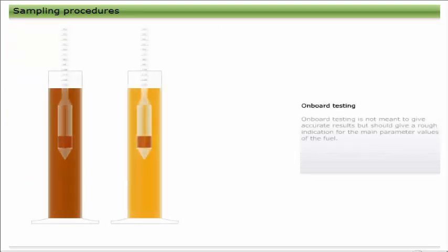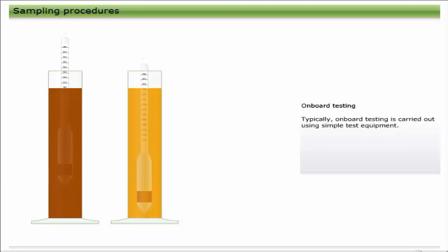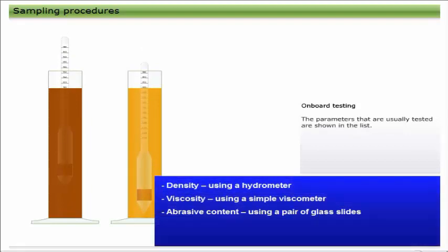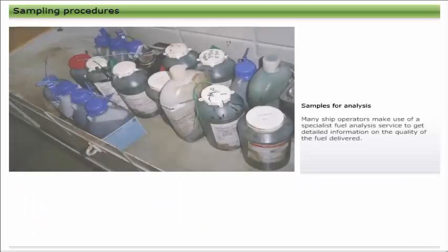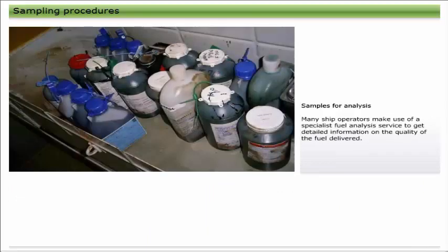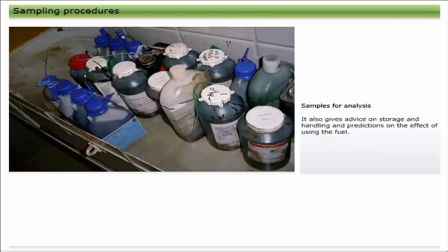Onboard testing is not meant to give accurate results but should give a rough indication for the main parameter values of the fuel, using simple test equipment. The results from these tests will give an early indication if using the fuel is likely to cause any operational problems. Many ship operators make use of a specialist fuel analysis service to get detailed information on the quality of the fuel delivered. The major classification societies offer this service and supply the containers, labels, and instructions for taking and forwarding the samples. The analysis report covers the fuel properties and contaminant content, and also gives advice on storage and handling and predictions on the effect of using the fuel. It is also good practice to carry out onboard testing as a check on the accuracy of the shoreside analysis report.